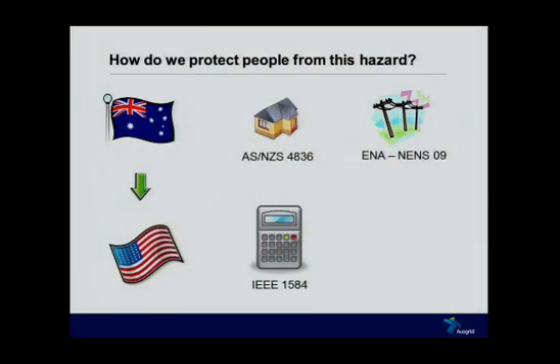There's two documents that go hand in hand there. One's IEEE 1584 - that's the engineer's calculation document that tries to calculate how big the boom will be if it goes kaboom. And then from that, NFPA 70E says this is the required level of PPE.